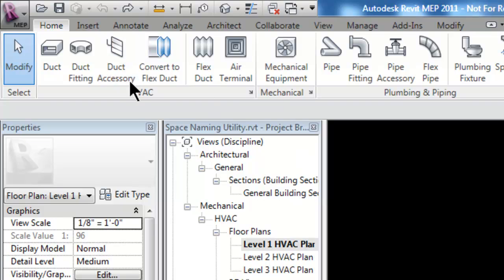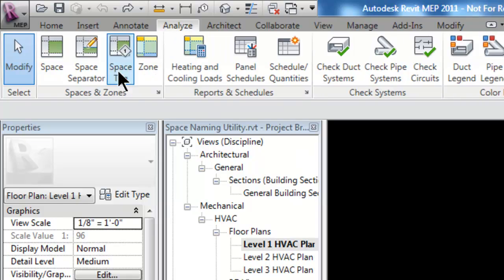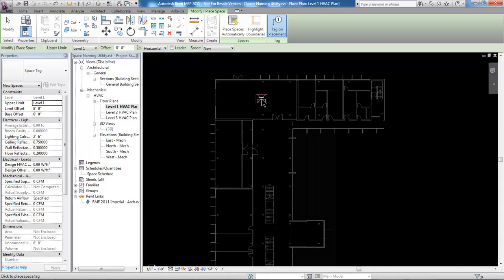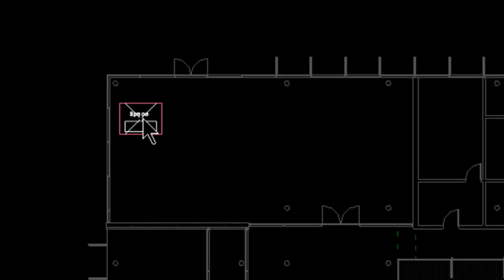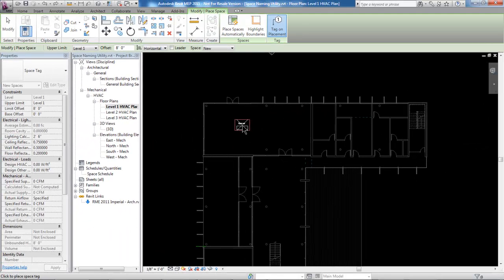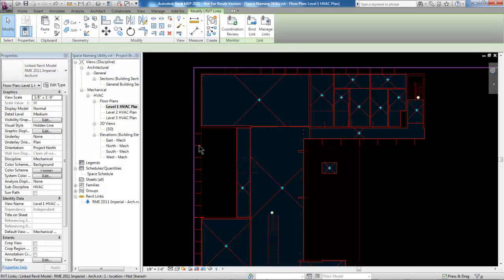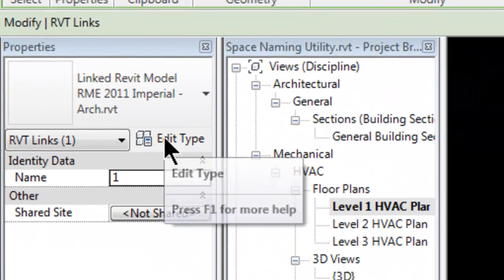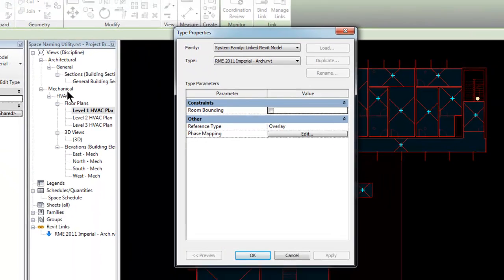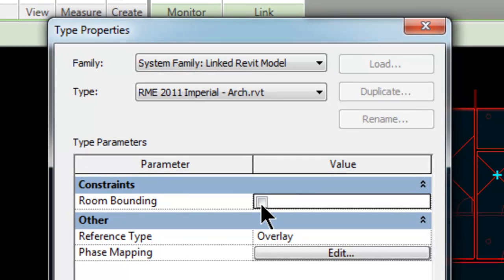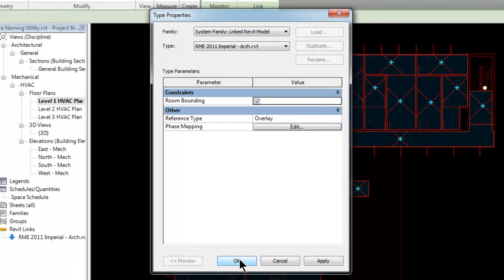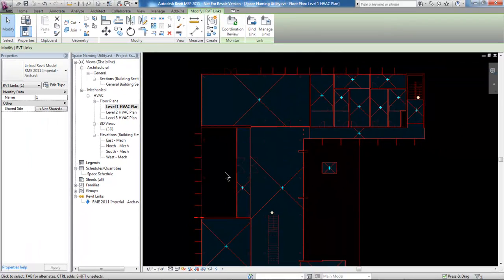If I go to the Analyze tab and select Space, I could attempt to place a space in a room on the model, but what's happening here is the boundary of the room is not being recognized by Revit. If I select the model, go into the Properties, and click Edit Type, notice that there is a room bounding radio button that has not been turned on. This constraint needs to be turned on for Revit to be able to create spaces using that architect's model.